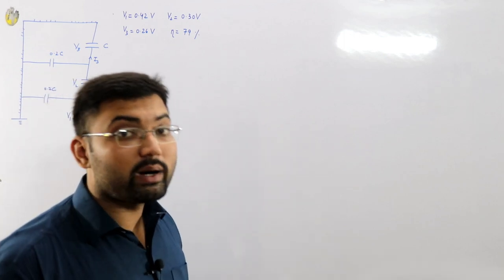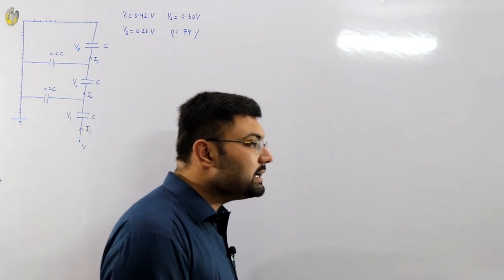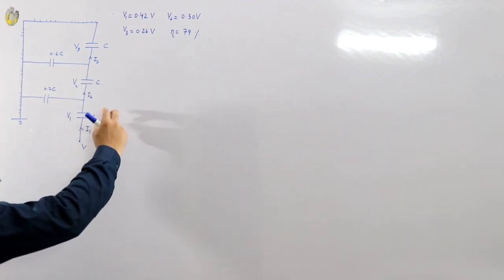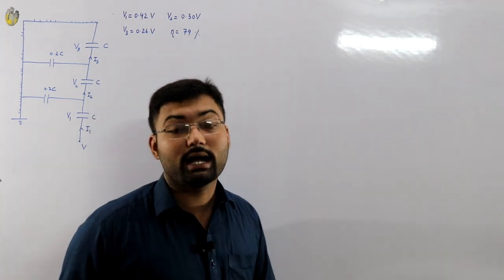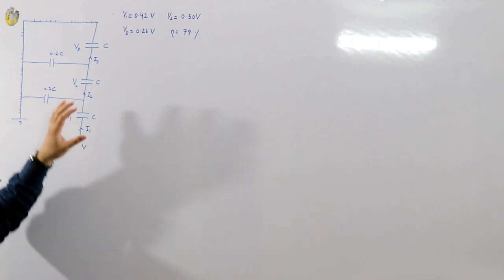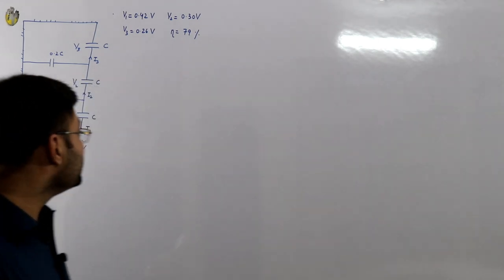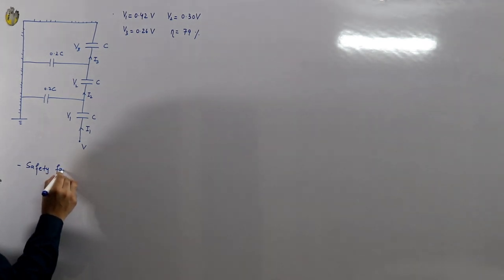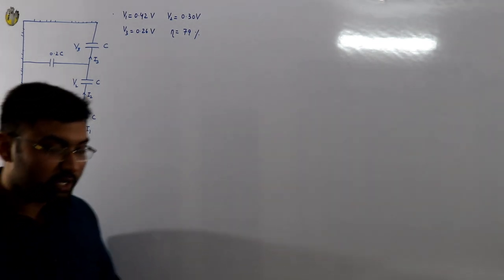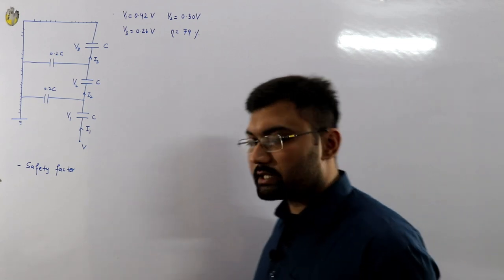In this video I want to improve string efficiency and reduce this non-uniformity. The first disc is over-stressed, so it has a higher risk of failure under power-frequency overvoltage. If it fails, the stress shifts to the remaining two units; the second then fails, then the third — this is called a cascaded failure. To prevent this, you can provide a safety factor by adding extra discs, typically a factor of two.